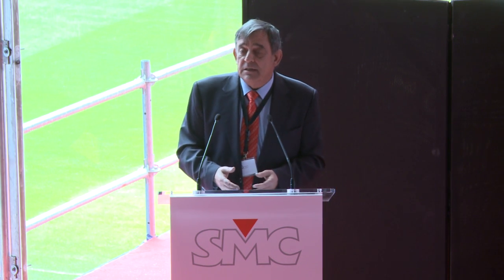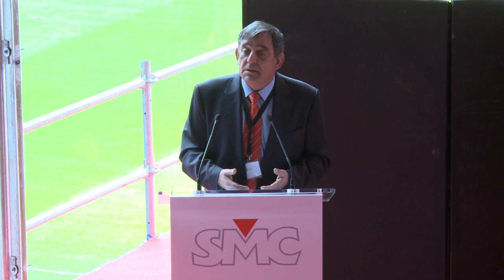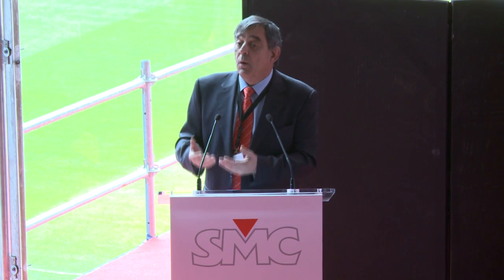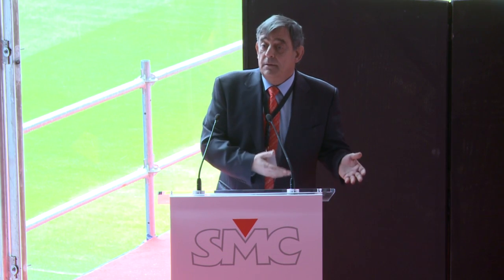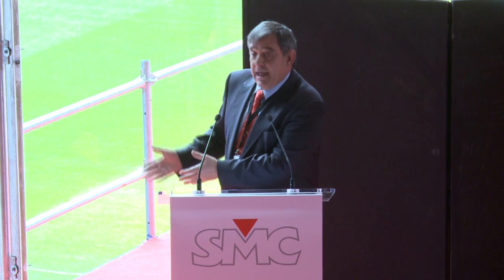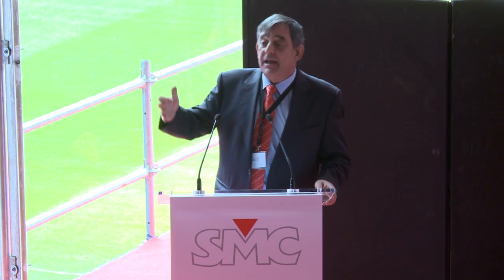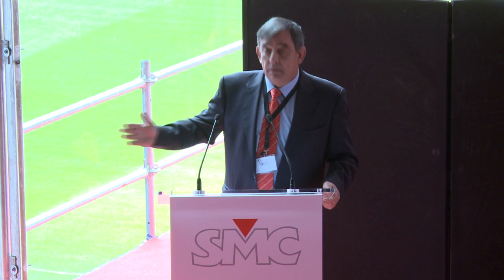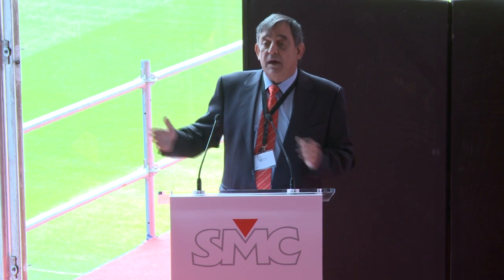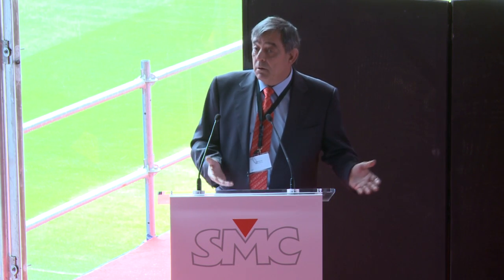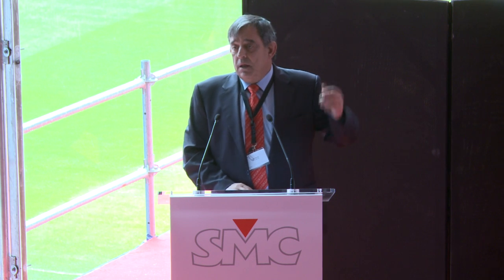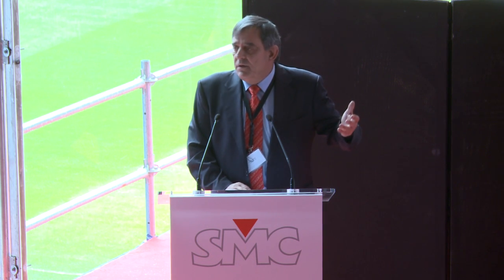So at the end, you are not bringing to the worksite all the secondaries available. You only bring the secondary that you need, and that's how you make it so light, because the secondary is elsewhere. By adding more slave units, you add compliance voltage, so you have more power, and you can go to something like close to 50 kVA.